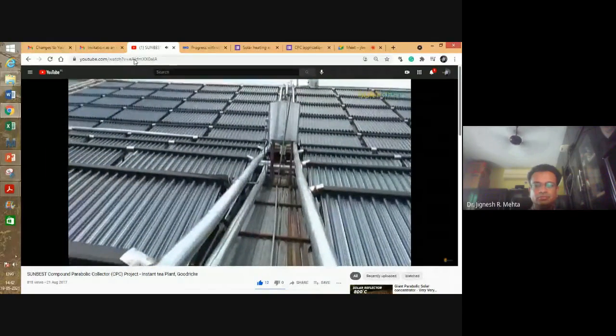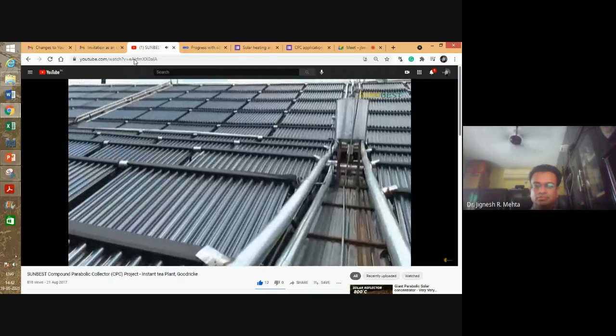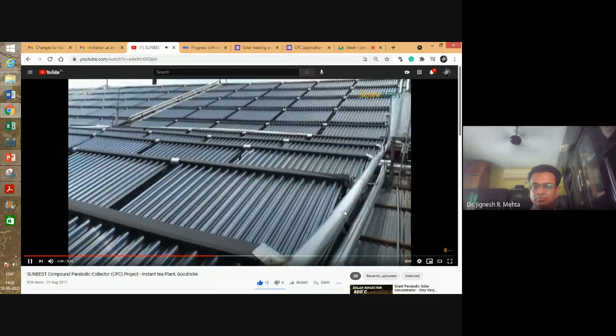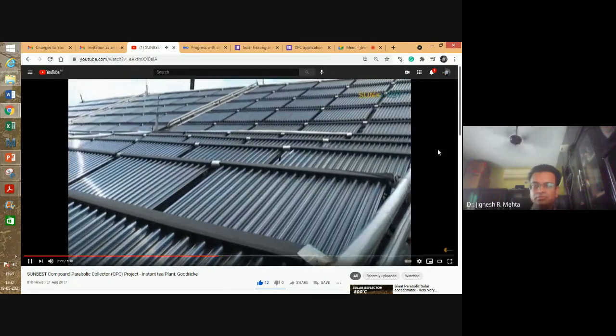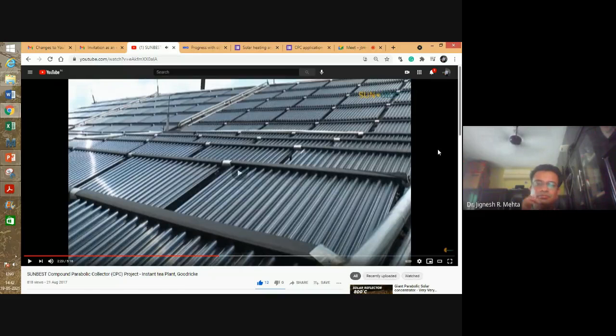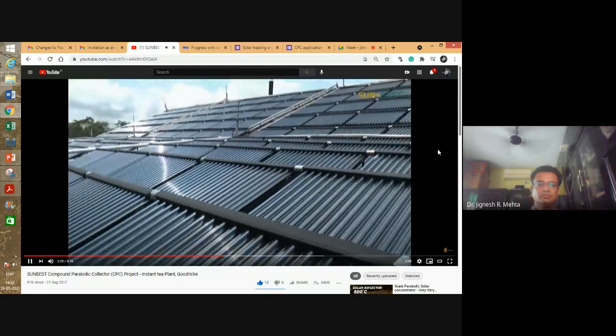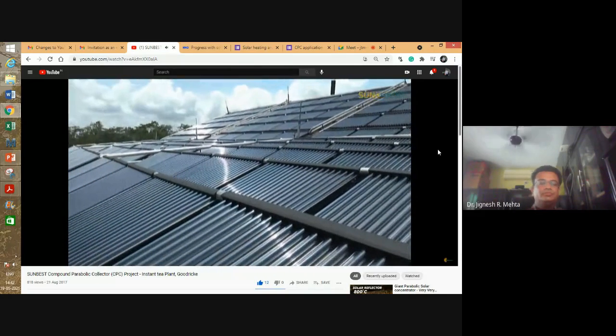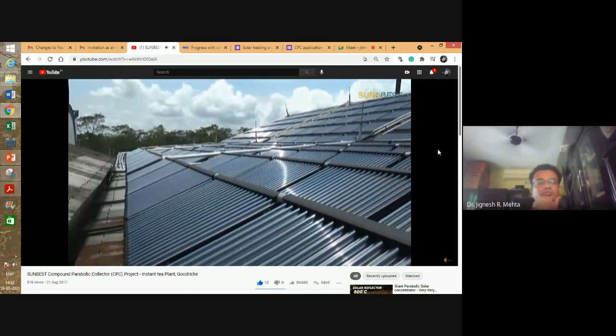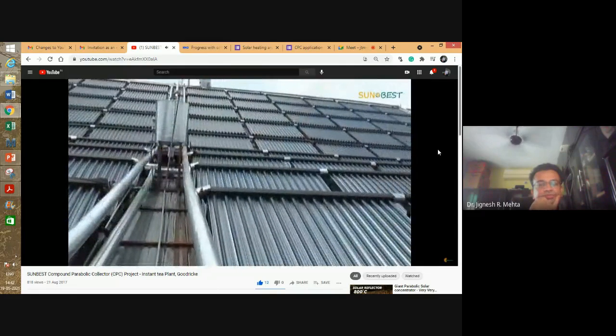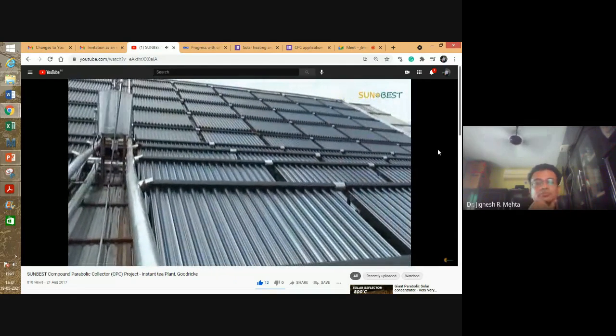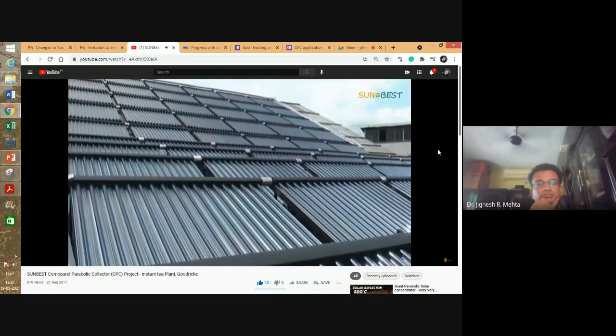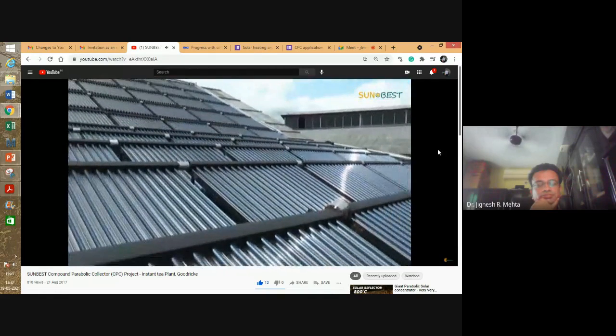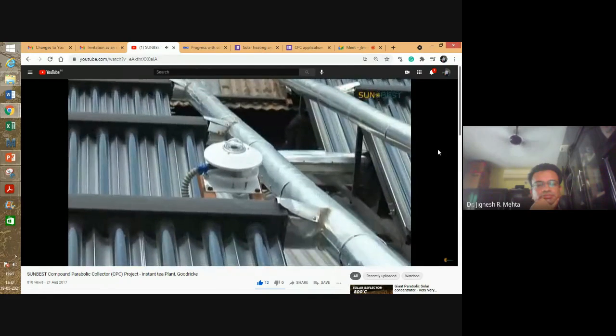One roof is carrying 107 collectors and the other roof is carrying 105 collectors, thus forming two different loops, which are passing through two different PHEs. During sunny periods, water inside the CPC collectors gets heated up by absorbing solar energy, and this hot water starts circulating inside the closed loop with the help of the pump.